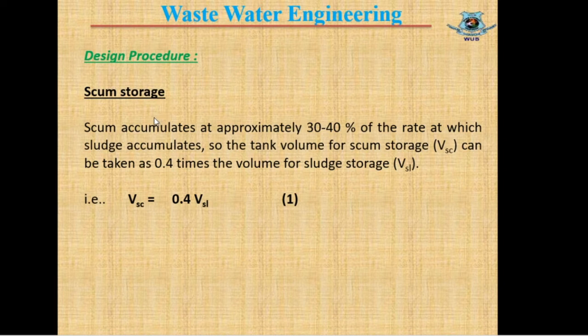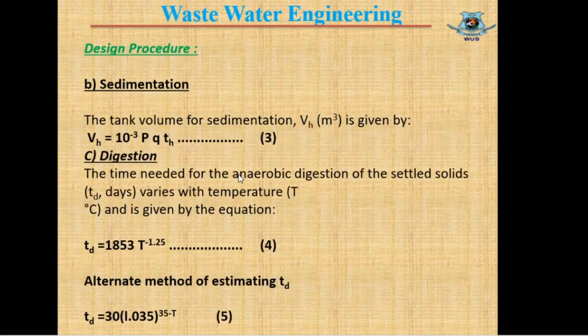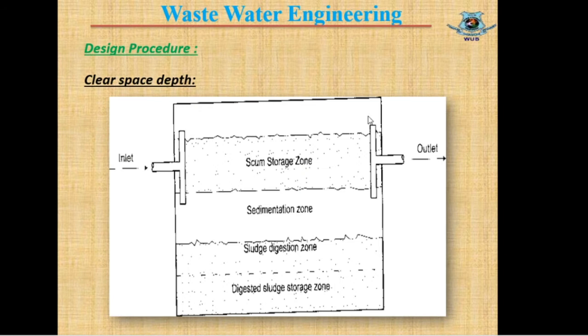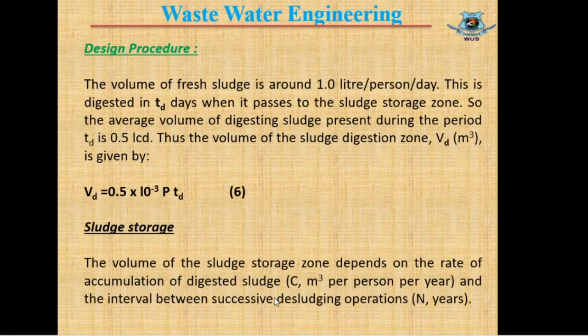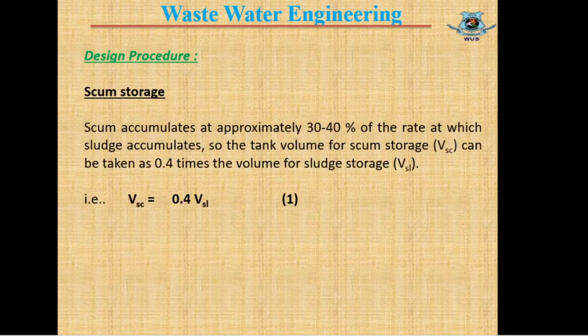The first design item is scum storage. Scum is the lightweight particles that accumulate at the top of the septic tank. Scum accumulates at 30 to 40 percent of the rate that sludge accumulates — that is, scum volume will be 30 to 40 percent of sludge volume. We take the maximum value of 40%, so the volume of scum VSC equals 0.4 × VSL (volume of sludge).